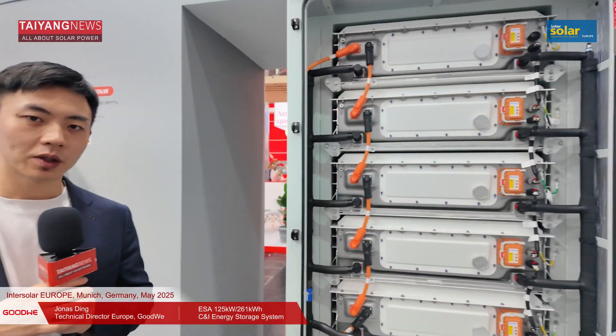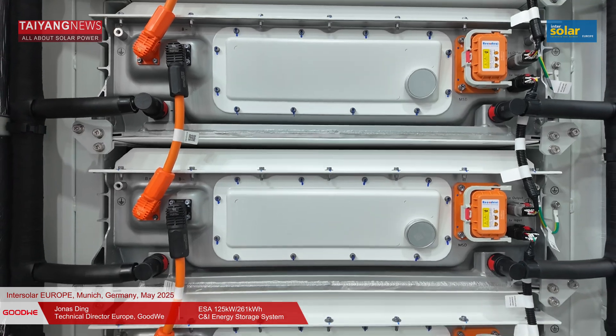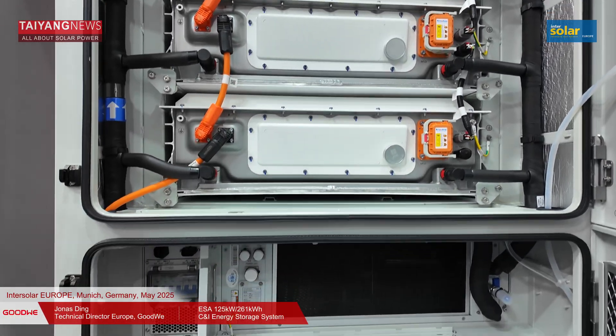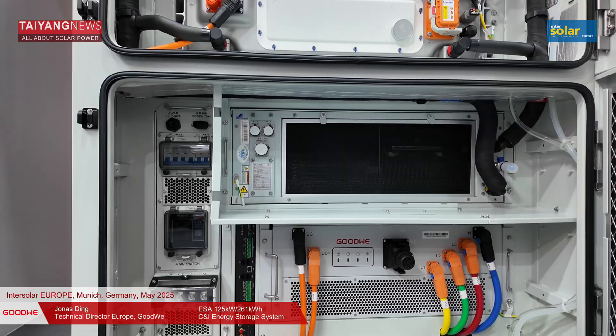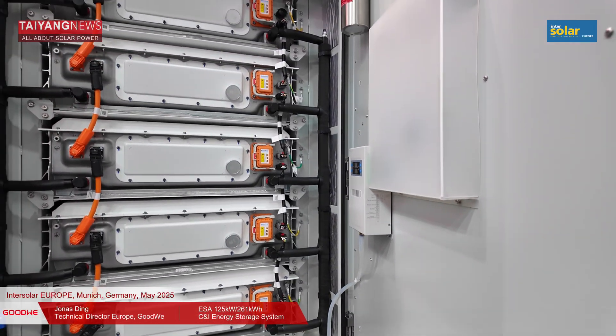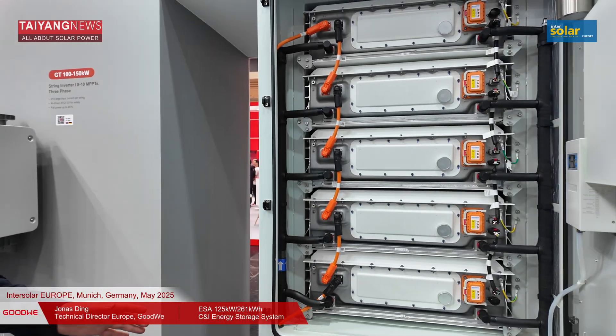GoodWe provides both DC-coupled and AC-coupled solutions. This particular product is an AC-coupled solution with 125 kilowatt PCS power and 261 kilowatt-hour battery capacity. It is a perfect solution for the dynamic frequency market, arbitrage market, integrating the GoodWe EMS or open-source third-party EMS. It is also a great microgrid solution with the STS box, able to work with a generator to build a microgrid with no concern about blackouts.